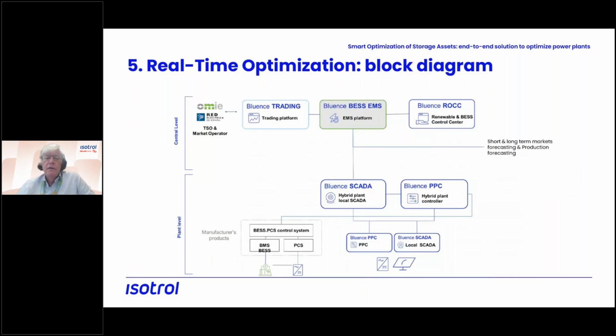For instance, this is a real case where you have an existing PV plant, and then you want to introduce batteries to the plant. So what you need is a master PPC and a hybrid plant controller, because you need to control the point of interconnection of the plant. You cannot allow the plant to inject more energy, the sum of the energy from the PV or the wind farm plus the battery, because you are not fulfilling what you are allowed to inject at the point of interconnection.